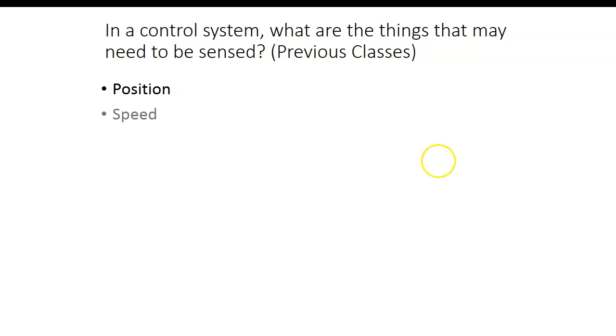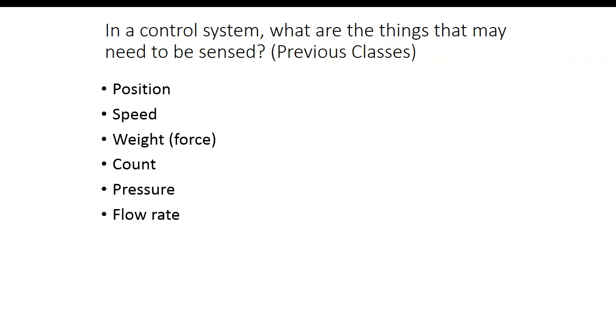So force, pressure, color, hue, contrast - there's a ton of things we might want to sense. This is something that we came up with: position, we talked about that; speed, we already brought that up, we sense speed all the time; weight would be a force; count, we came up with that one; pressure; flow rate - flow rate is how fast the fluid is moving. So on your fluid power actuators, your pressure determines the force, your flow rate determines the speed, right? So we need to sense that.